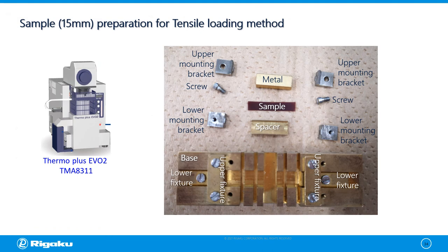This slide shows a kit used for the preparation of a sample for tensile loading method. The sample lengths you can set are 10 mm, 15 mm, and 20 mm in length. Next is a video showing how to mount a 15 mm sample for tensile loading method.